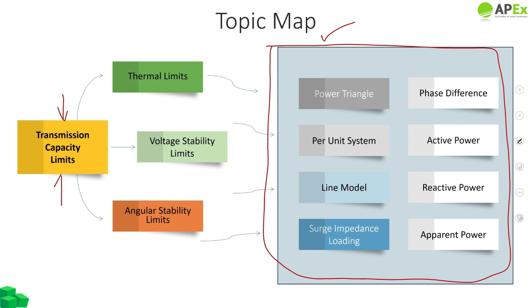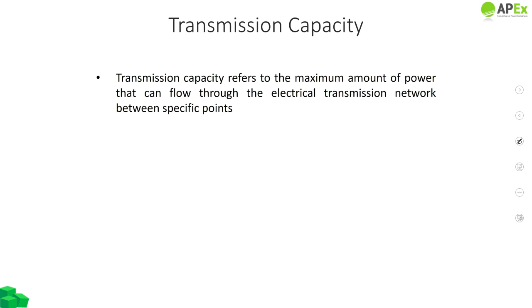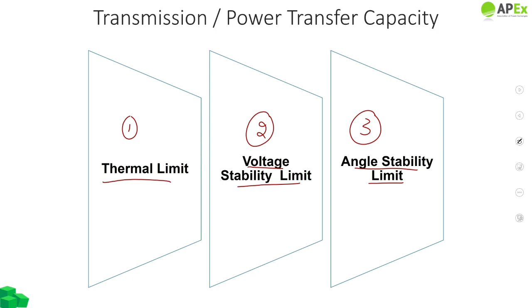So what is the transmission capacity? Transmission capacity refers to the maximum amount of power that can flow in an electrical transmission network between two specific points. The transmission or power capacity is limited by three important considerations: the thermal limits, the voltage stability limits, and the angular stability limits. We will cover all of these in the very same order. First we'll cover the thermal limits, then the voltage stability limits, and then finally the angular stability limits. And there is a reason why this goes in this order.